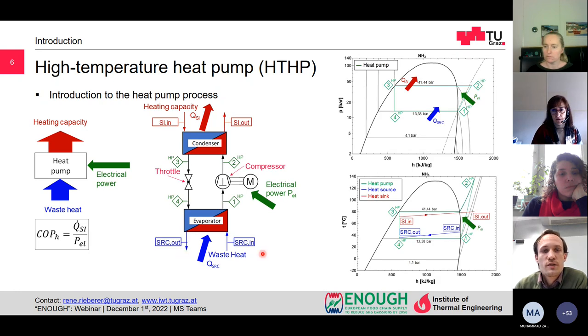Here the process is also shown in a TH or a pH diagram. We can see that the refrigerant from state point one to state point two is lifted in pressure before it is condensed here in the condenser by releasing heat to the heat sink, and then the refrigerant is throttled to the low pressure, and afterwards it's evaporated here in the evaporator. You can also see the reduction of the heat source temperature and the increase of the heat sink temperature.